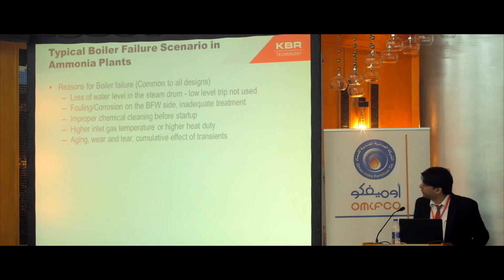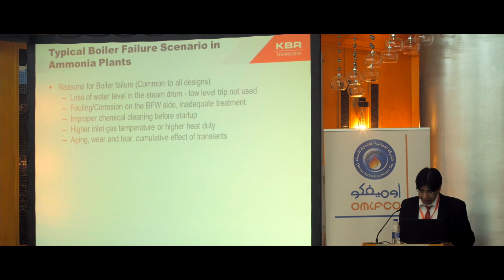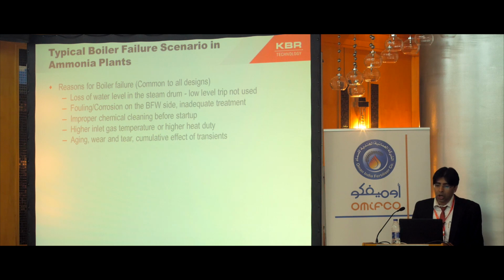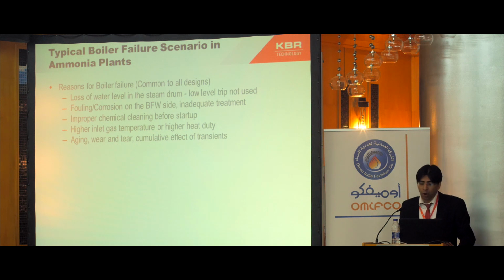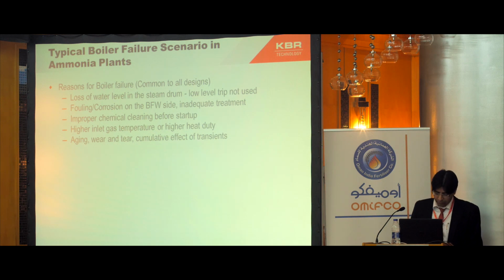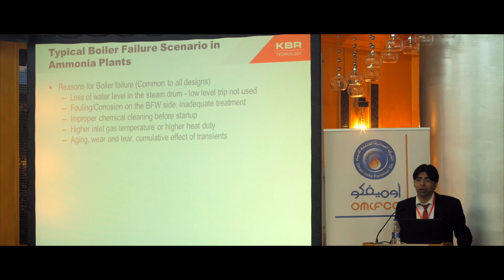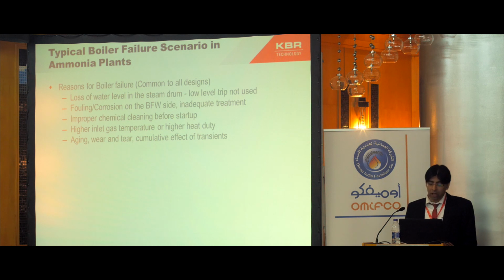For this kind of service, all boilers will probably eventually fail. KBR designed boilers and competitive boilers fail for the same reasons. Common reasons for the failure are loss of water level in the steam drum, which is due to boiler feed water pump trip, loss of dilution steam in the feed, which results in high process gas outlet temperature leading to corrosion, or loss or out of spec BFW, which results in fouling. The instrumentation and the controls and the operating procedures are provided to minimize the chance of these failures, but accidents do happen.